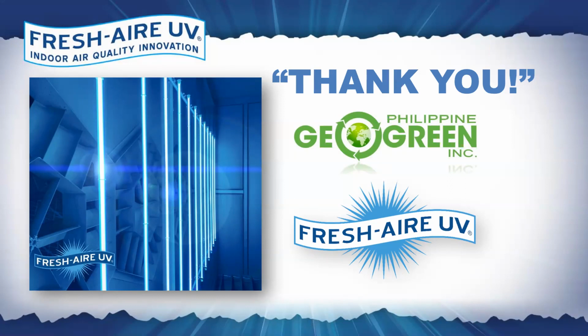Well, it depends. On the mini LED—which for some reason I didn't include in the presentation slide—we have a mini LED strip that operates at a different frequency than the 254 nanometer we've been discussing, between 400 and 405 nanometers. It works on a different principle, is completely safe to look at, and has no issues with plastic degradation or similar effects. So there's no proximity issue with that system. Conventional UVC at 254 nanometers is something you do not want to subject yourself to, but that wavelength of light is inside the HVAC system and not an issue for occupants.